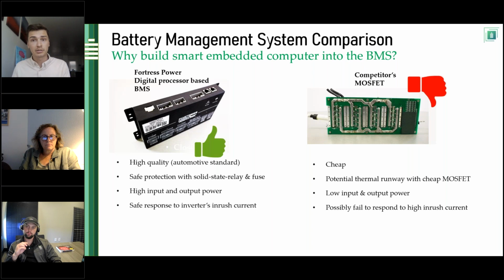You want a BMS like the one on the left, a digital processor-based BMS with a solid state relay and fuse. That means there's a fuse that will open the contactor, and there's no way that power, if that contactor opens, is going to get from the energized source to the battery. It's a very safe, robust battery management system that opens that contactor and says no more power, protecting my prismatic cells.